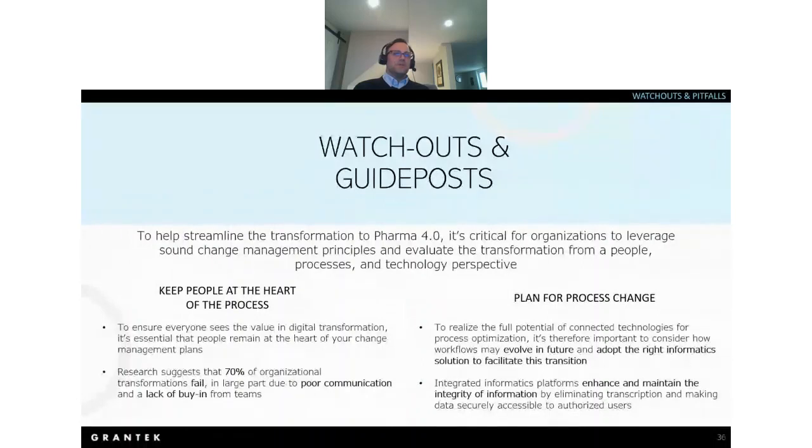For example, in a QC lab, with equipment connected via a laboratory information management system, or LIMS, laboratory professionals can download instrument parameters direct to the equipment itself, eliminating the errors associated with manual setup and making analysis faster.